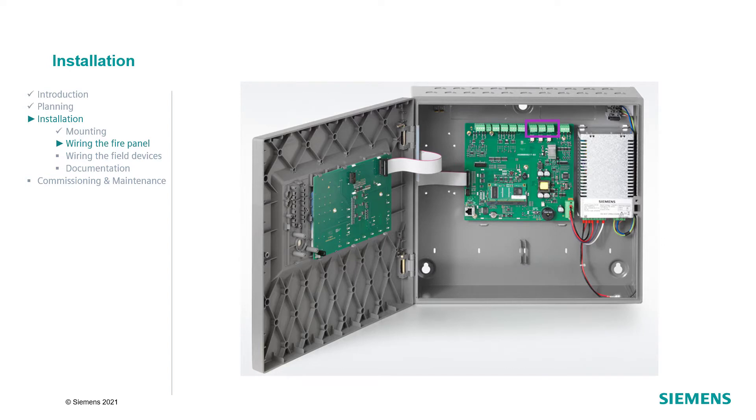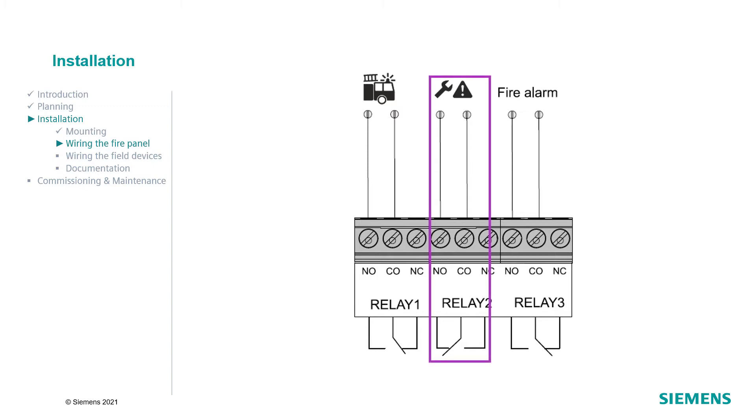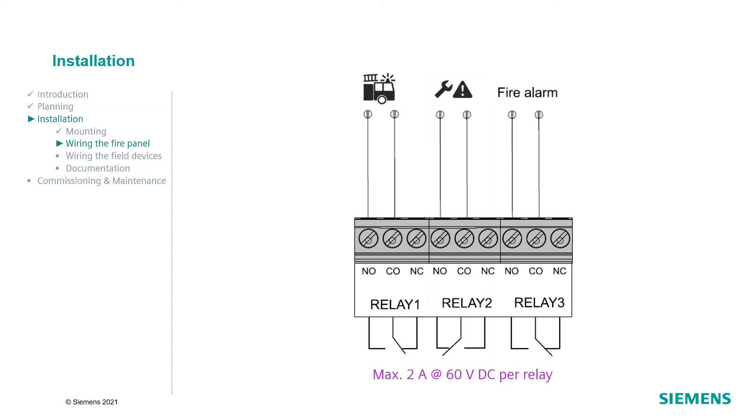The panel main board contains three relay outputs used for controlling without line monitoring. These relay outputs can be freely configured as fire control, remote transmission fire, remote transmission fault and fire alarm. Connect the normally open or the normally closed outputs and the common connector depending on your requirements. The output remote transmission fault is closed as an inverse function in quiescent mode. In case of fault, the contact opens. The maximum current of each relay is 2A at 60V DC.